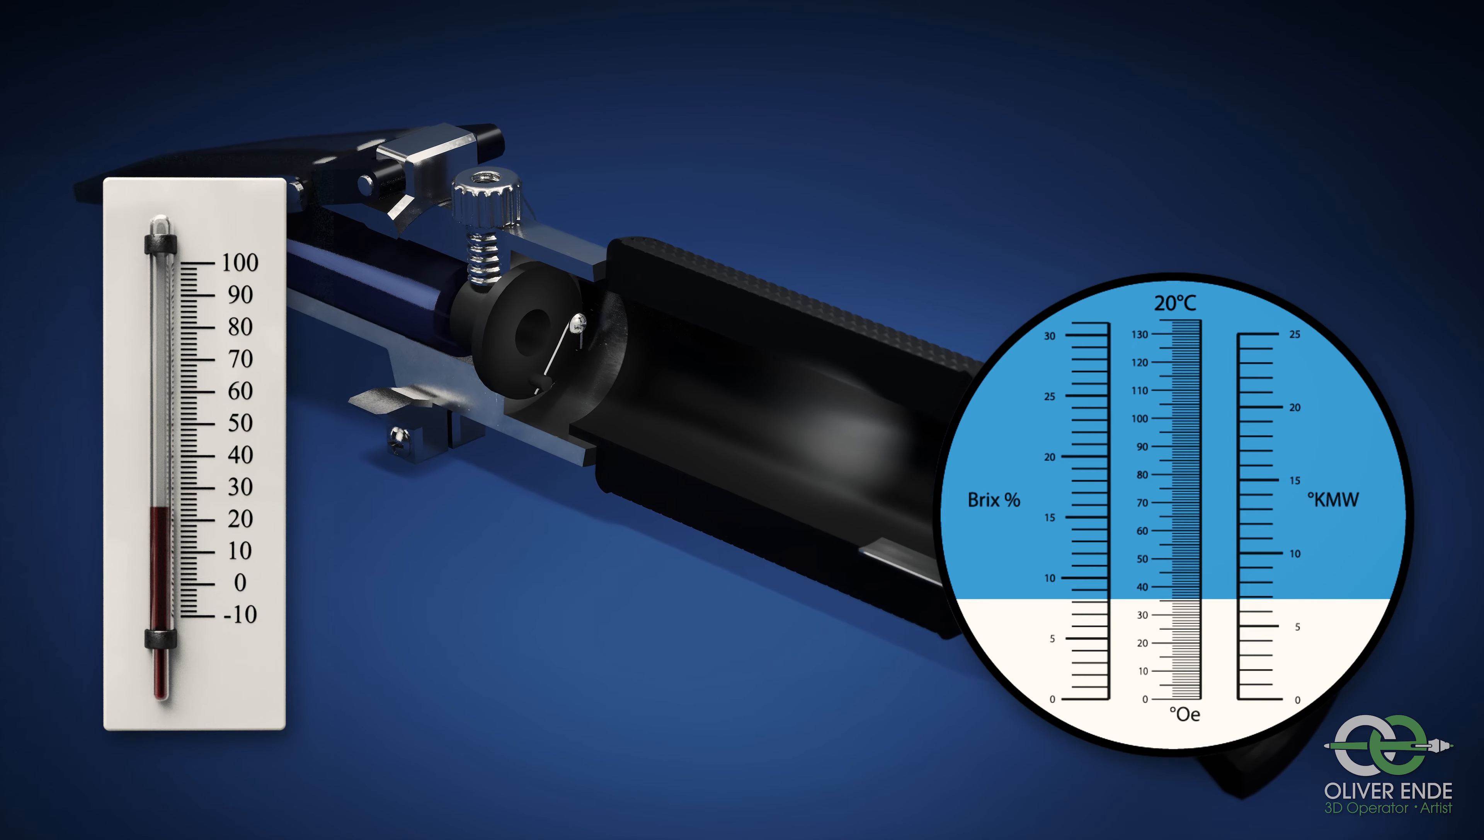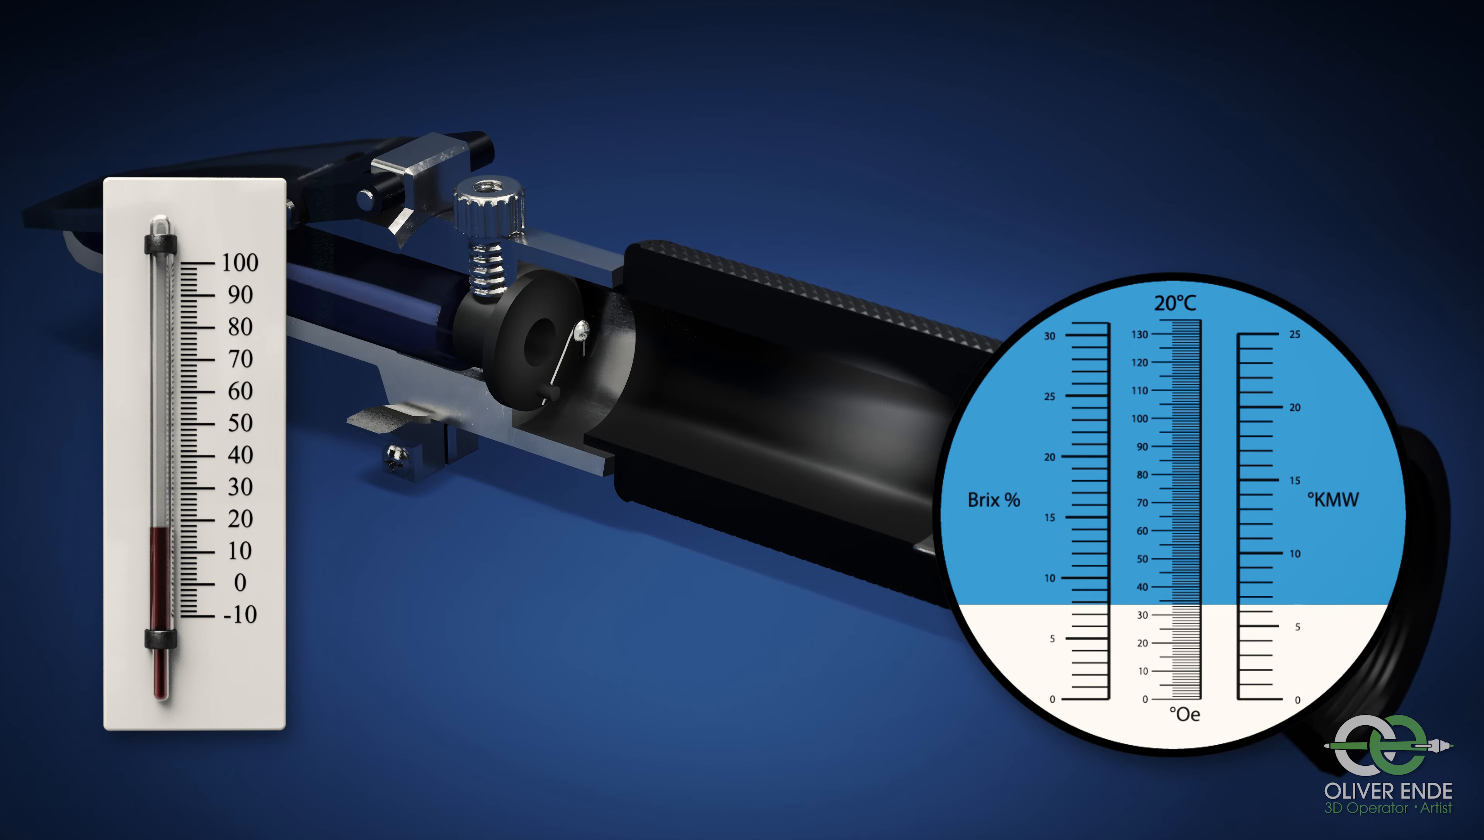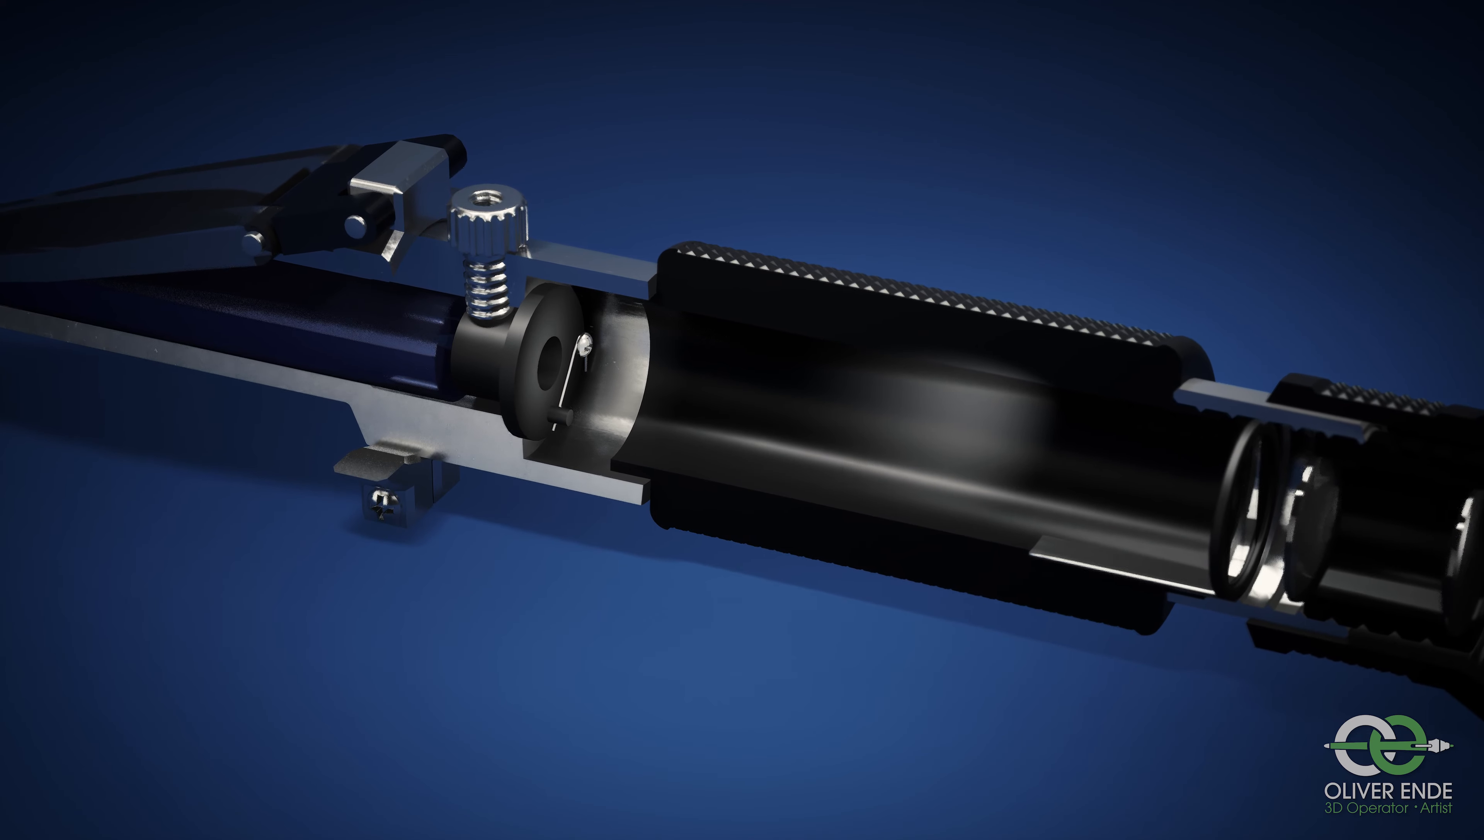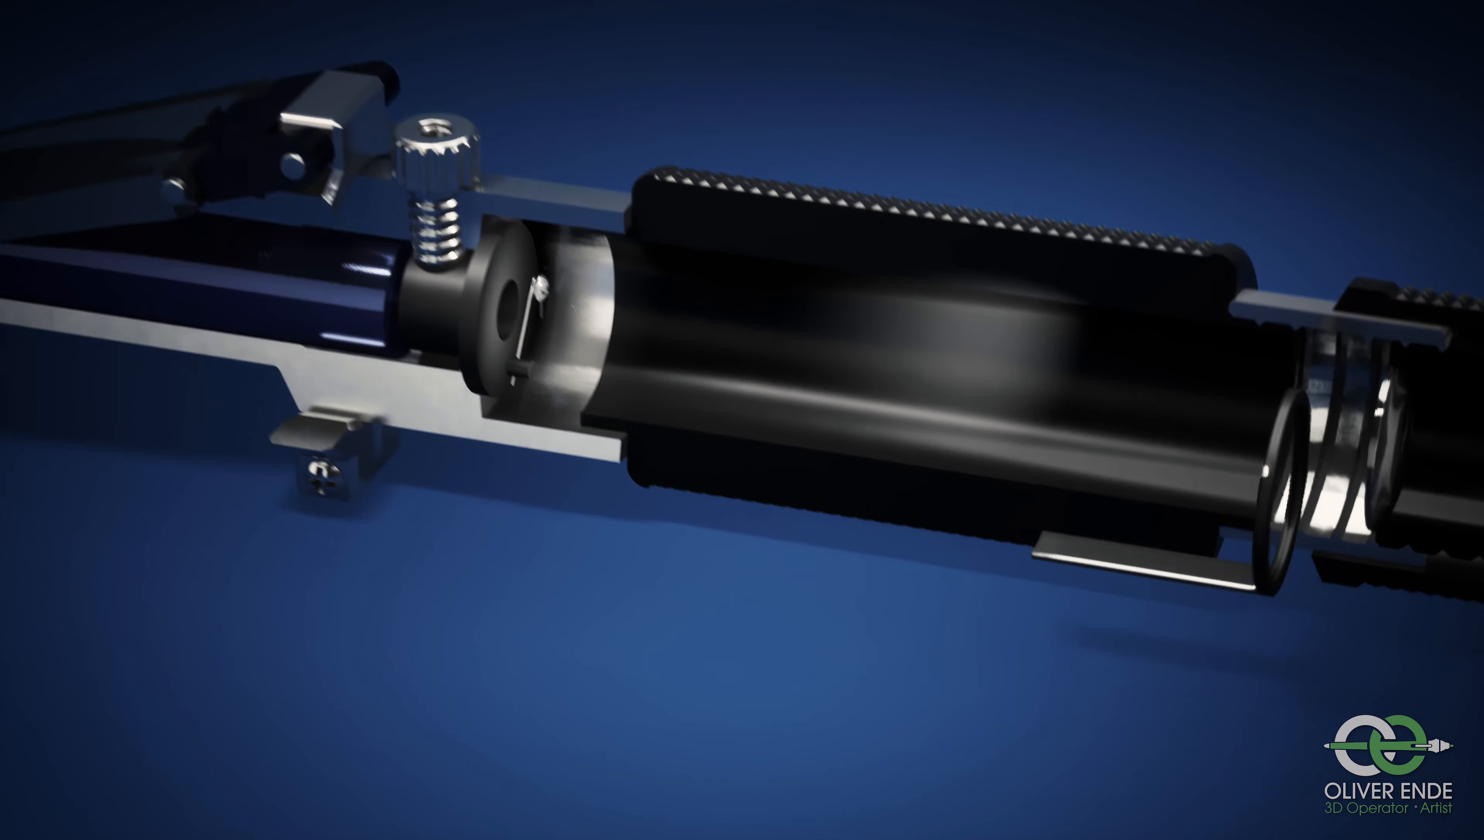If you measure the same liquid at different temperatures with a refractometer, you will get different results. The temperature therefore has an influence on the accuracy. To compensate this difference, there is a so-called automatic temperature compensation, also called ATC. The measuring scale is mounted on a bimetal. Depending on the temperature, the bimetal aligns the scale accordingly.